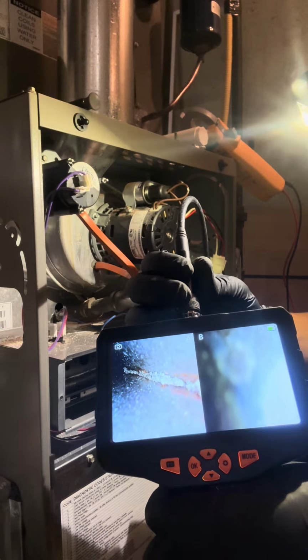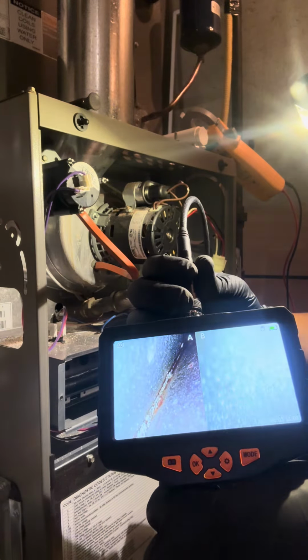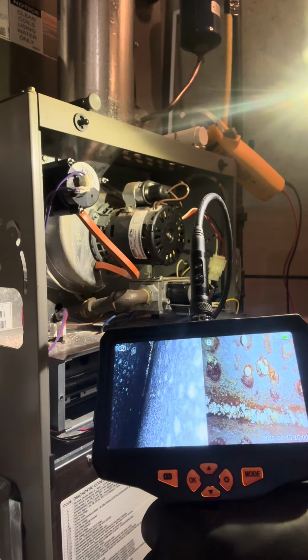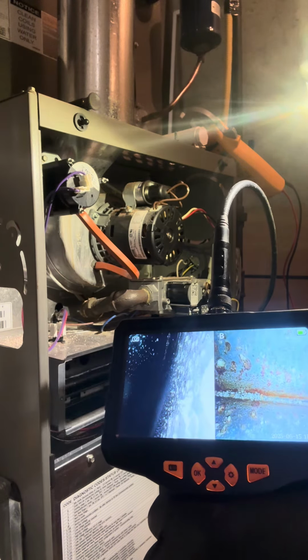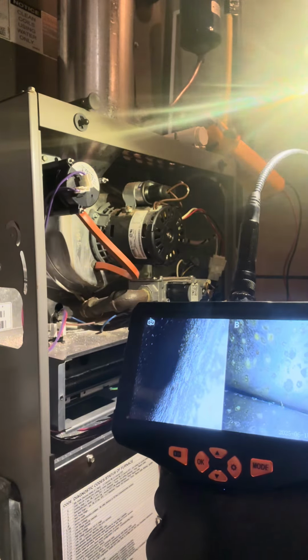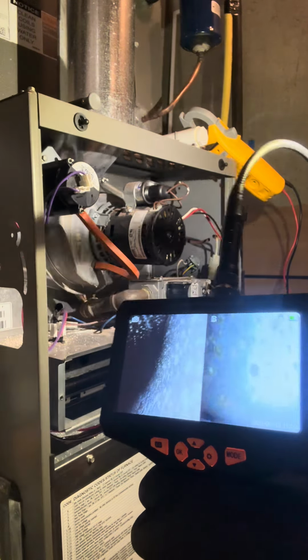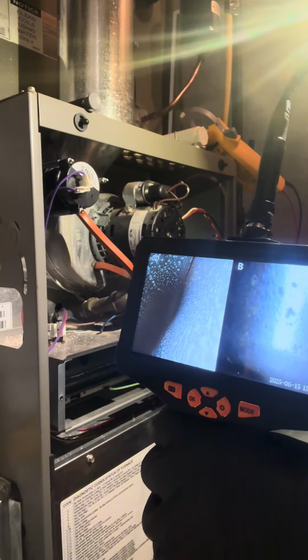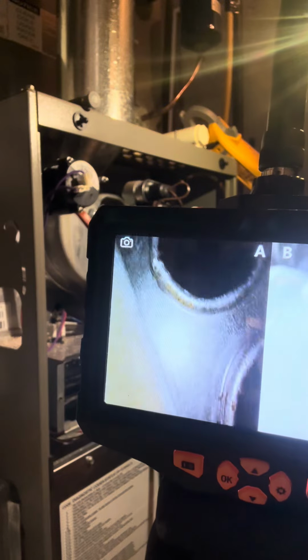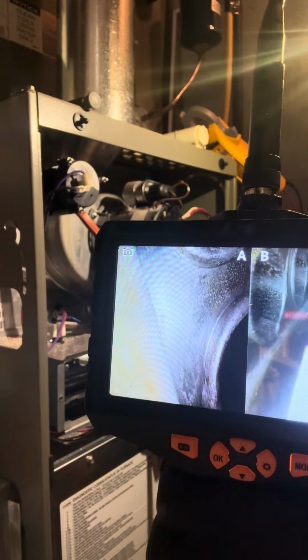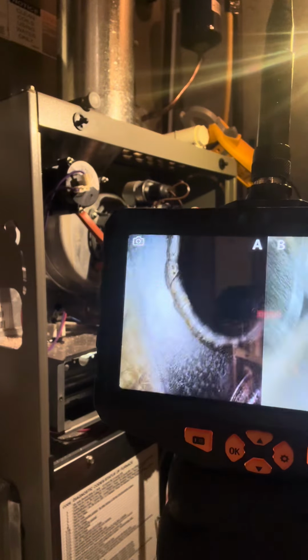The way these heat exchangers are designed, they're designed as a serpentine style clamshell. So they take two pieces of metal and they clamp them together in the S form, and your flames shoot through these tubes. So obviously when the flames hit the back of that heat exchanger is when you're typically going to see the most heat and the most corrosion, and also typically where you'll see your cracks. And these are the tubes that the flames shoot inside, as you can see.